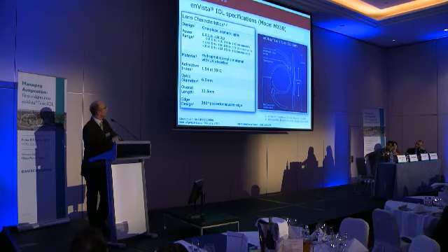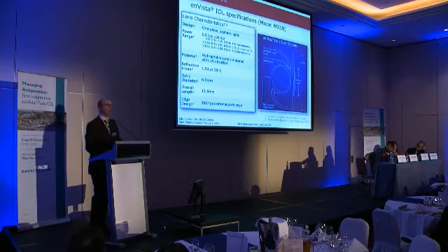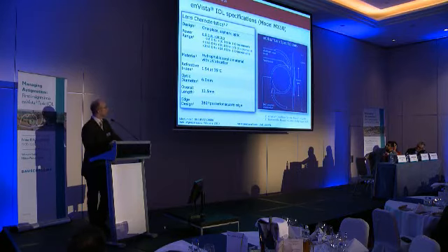It is a hydrophobic acrylic material, obviously with a UV absorber, 6 millimeter optic, 12.5 overall, so very straightforward. Open loop design. This material has been around for a while, so people like Manfred Tetz from Berlin have tested these materials and have long-term follow-up, and he may want to discuss that in the discussion section later, where this material has been shown to be glistening-free and also very, very stable.